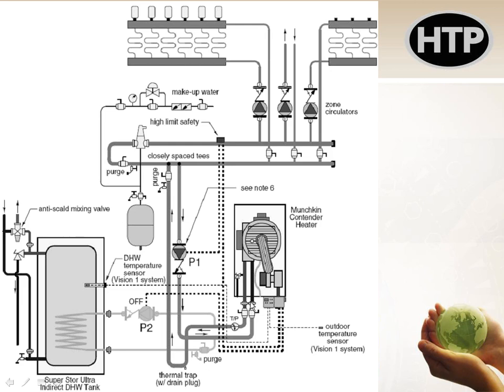And then coming off the bottom of him is my supply and return piping. And you can see as that loops around, there is a pump labeled as P1. And then up to the top here where the closely spaced T's are, and loops back around. So between the boiler through that pump is one loop right there. All right. I have a second loop in this case, right? So I have my primary loop at the boiler, and I have a second loop out in the space that's circulating throughout my house or throughout my building with all my various zones on it.